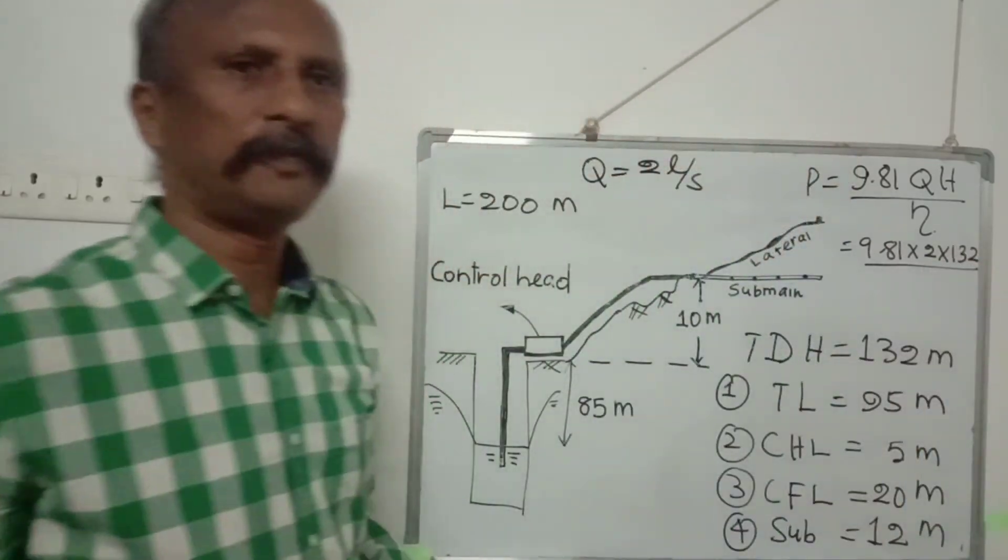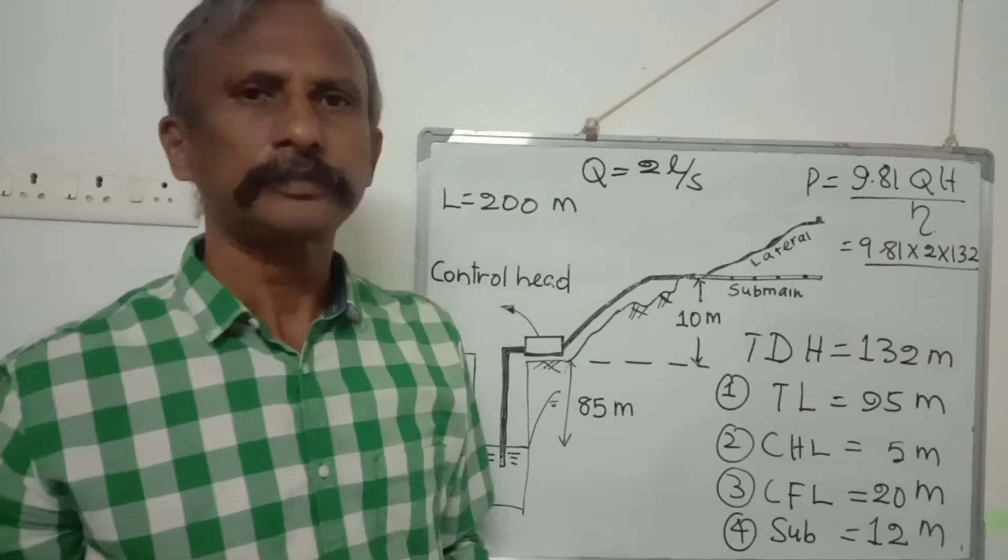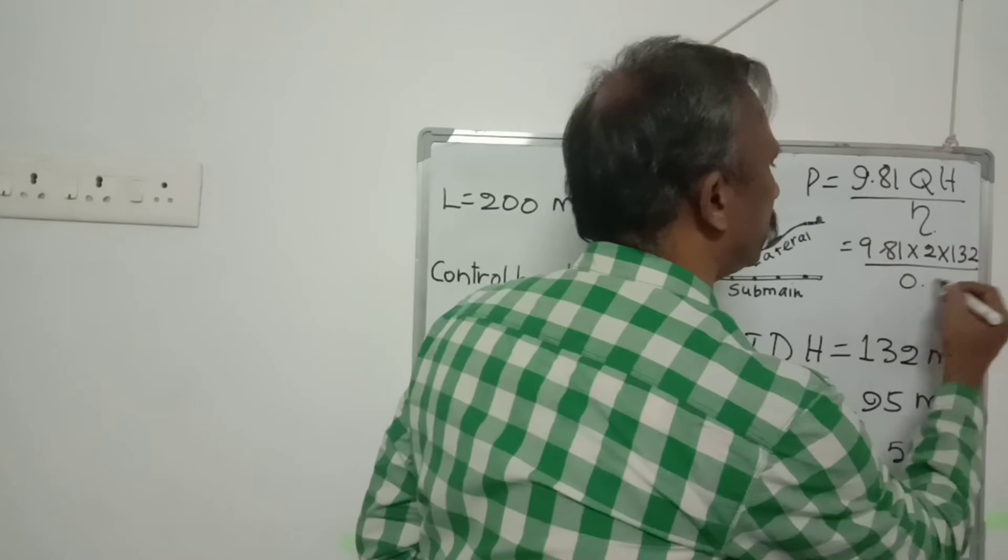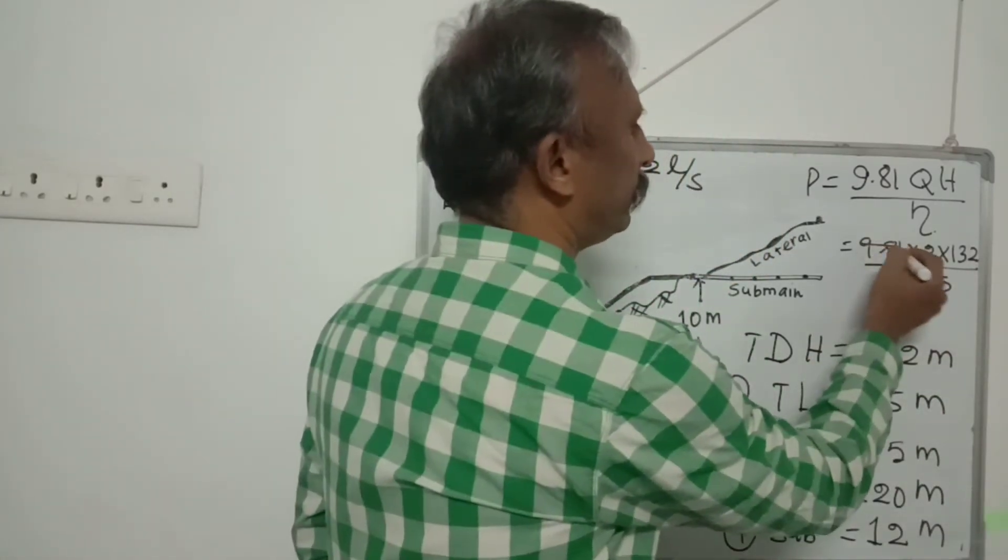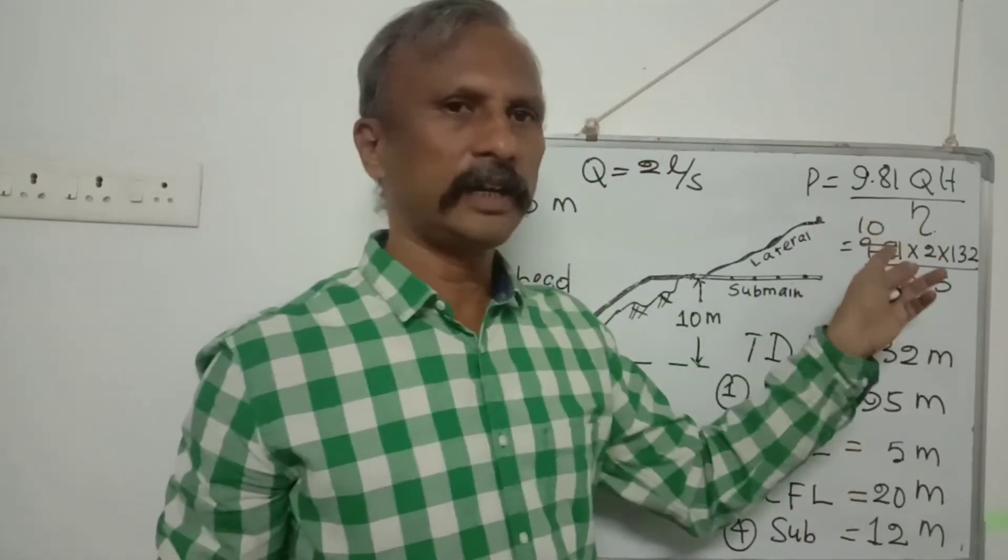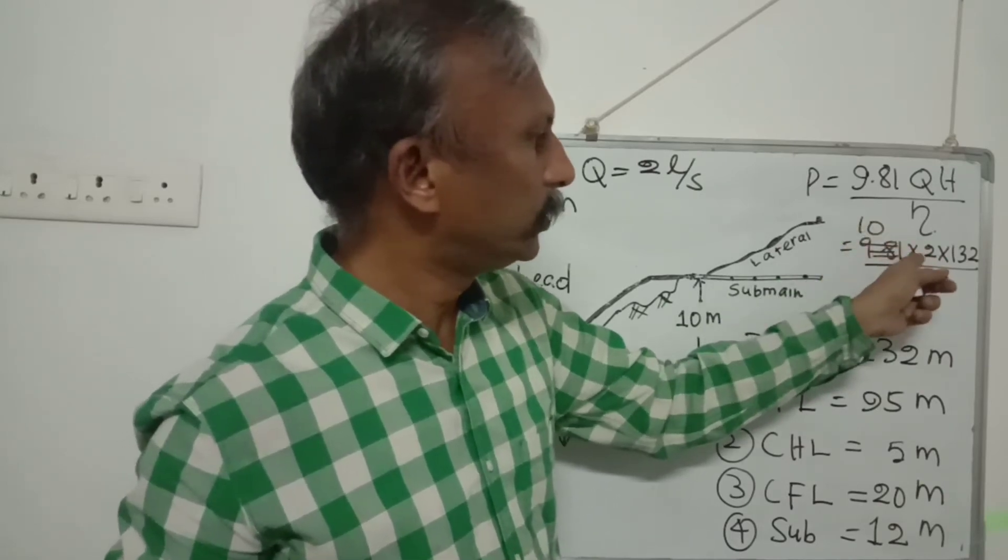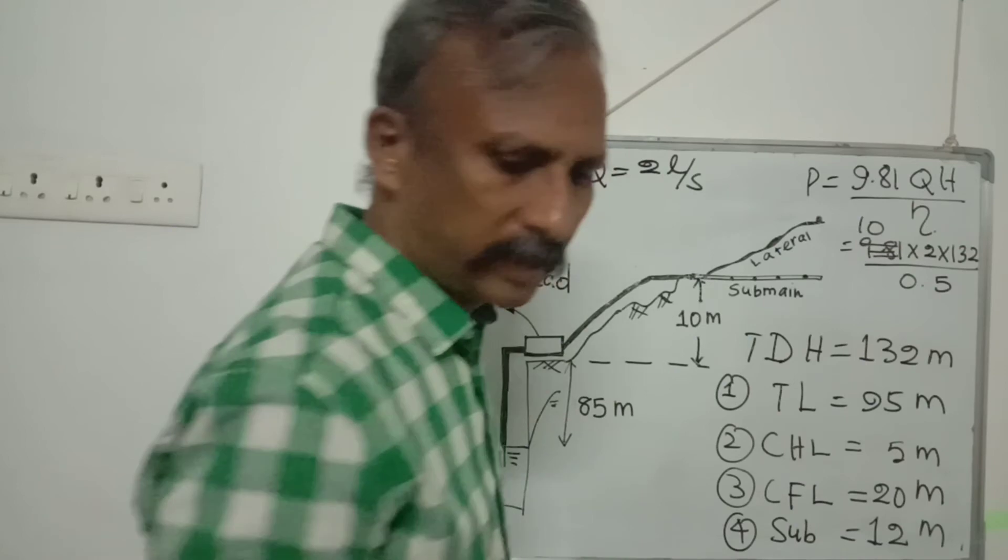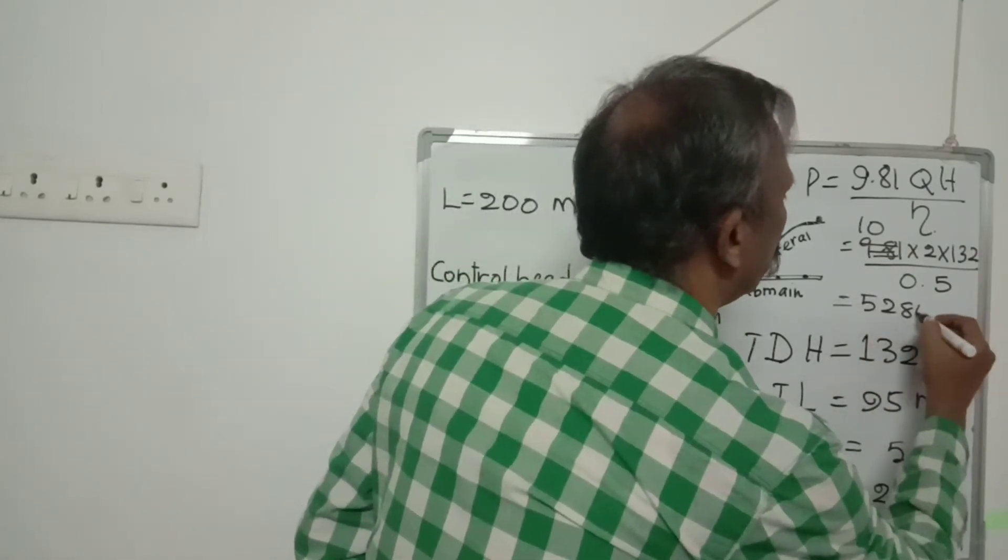The efficiency of the pump varies between 0.5 to 0.7. It is customary to take the lowest efficiency. If you take 0.5, and instead of 9.81 you can assume that to be 10 for simplicity in calculation, 10 × 2 × 132 divided by 0.5, you will get 5,280 watts.